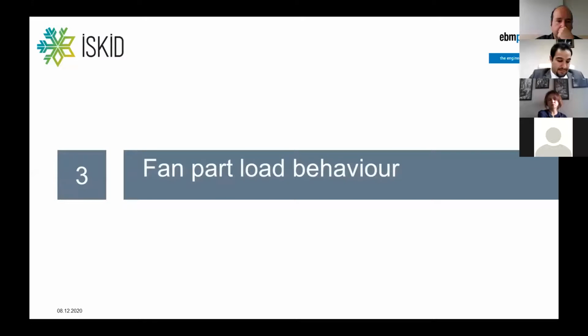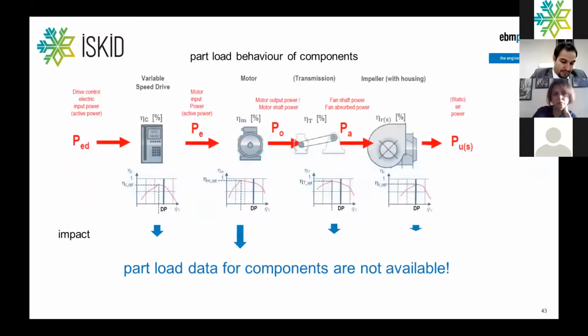Coming to another point that is very critical, because it's hard to judge fan part load behavior. There are so many components included in a fan. It's not only the fluidic flow machine, the fan itself. As shown before, it's also the drive, the motor, the transmission if there's one, and the fan itself. So it's very easy to calculate the fan data, and when reducing the speed, the efficiency doesn't change very much. But this is not the case for the drive. It's not the case for the motor, and also not the case for the transmission. The most critical thing is these part load data for components are not available.